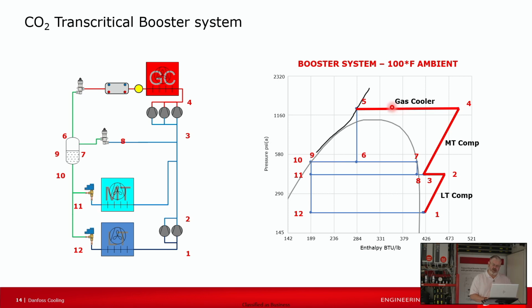Just to note before we continue, if we were showing the 65-degree ambient, that gas cooler is certainly operating as a condenser, but it gets the nickname gas cooler and people just stick with it. So I mentioned earlier, we have an expansion where we flash gas off. That's our high pressure valve going from point 5 to point 6. So that brought us back into the dome. And you can see here that our percentages kind of line up. We're roughly 45% vapor here, about 55% liquid in the flash tank.